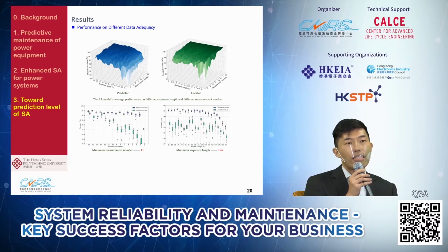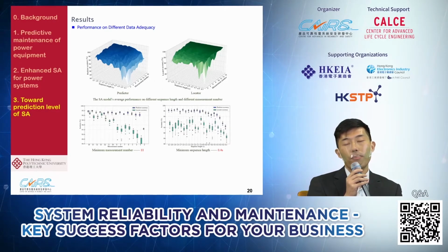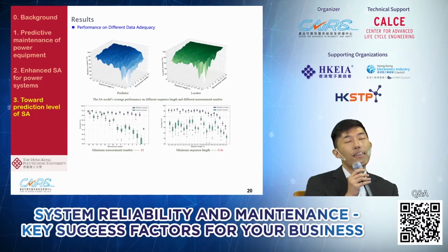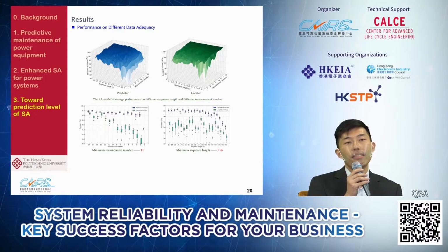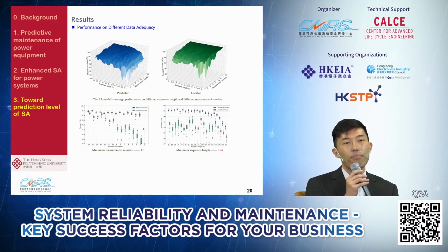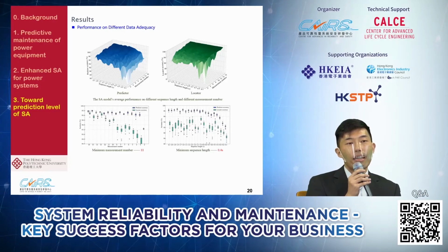We also looked at some practical factors. For example, we tried to decrease the number of PMUs, and also decrease the time period of data after the fault. These are, respectively, a spatial feature and a temporal feature, and decreasing both contributes to lower prediction accuracy. But we found that to achieve an acceptable level, it's better to have 11 PMUs deployed in the system, and the minimum length of data should be 0.4 seconds.